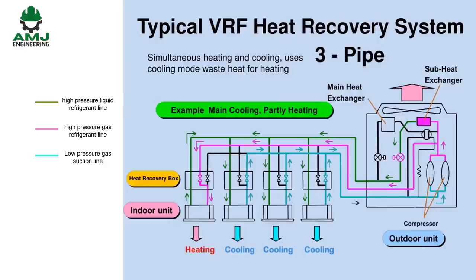In this system, each outdoor air-cooled condenser is connected via 3 pipes to an indoor heat recovery unit. A high-pressure gas refrigerant line for heating, a high-pressure liquid refrigerant line for cooling, and a low-pressure gas suction line for return to the outdoor unit. Each indoor heat recovery unit works together with the indoor terminal units and respective thermostats in each zone to determine if they require heating or cooling. An indoor terminal unit in heating mode is supplied with high-pressure gas refrigerant from the heat recovery unit. The heating mode indoor terminal unit acts like a condenser, and the refrigerant exits as a high-pressure liquid and proceeds back to the heat recovery unit.